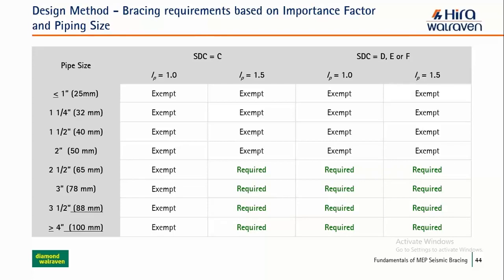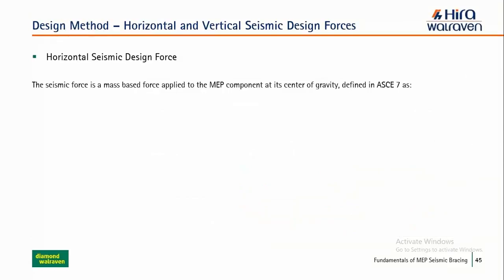For design categories D, E and F, both 1.0 and 1.5 are required for the same size, as with a 3-inch pipe. In design category C, 1.0 is exempt and 1.5 is required, but in D, E and F it's required for both 1.0 and 1.5 for these sizes. If a smaller size requires this, the higher sizes shall also be involved. This is the concept to categorize pipe sizes and differentiate seismic requirements based on seismic design categories.